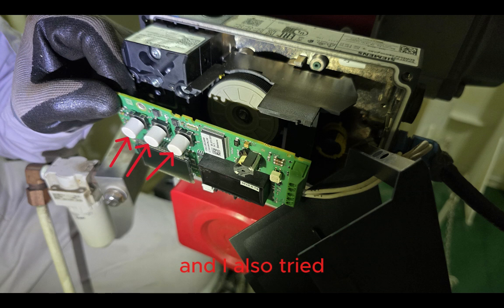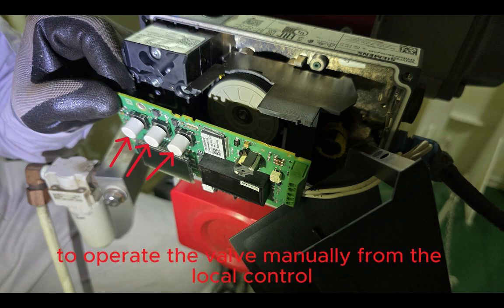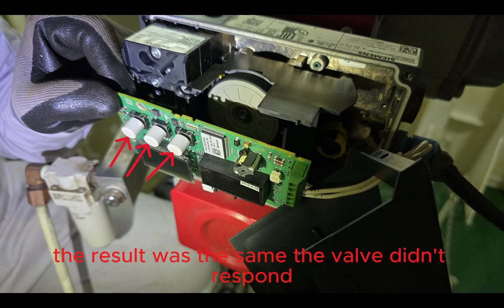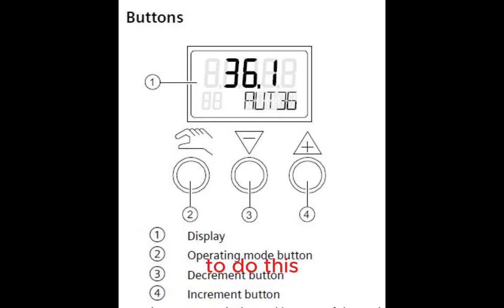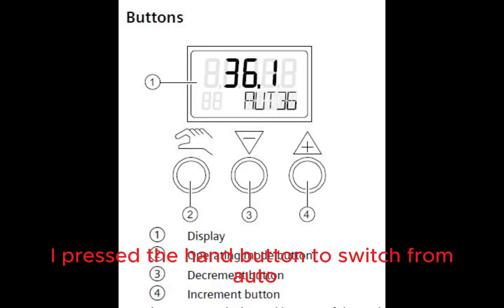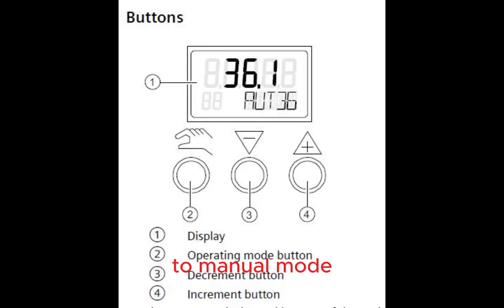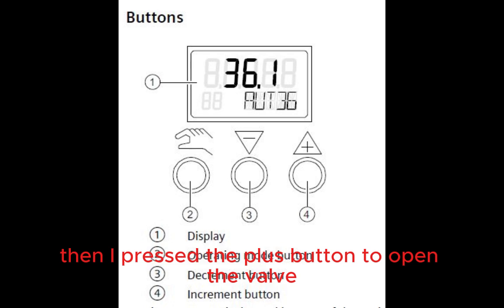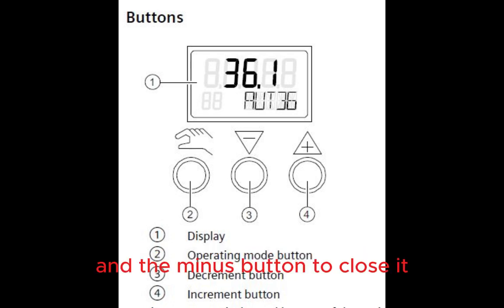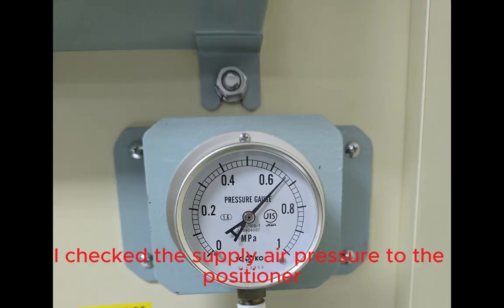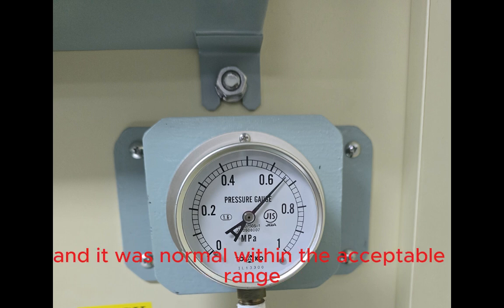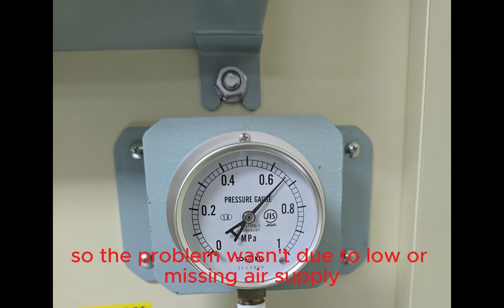And I also tried to operate the valve manually from the local control. The result was the same, the valve didn't respond. To do this, I pressed the hand button to switch from auto to manual mode. Then I pressed the plus button to open the valve and the minus button to close it. I checked the supply air pressure to the positioner and it was normal within the acceptable range. So the problem wasn't due to low or missing air supply.